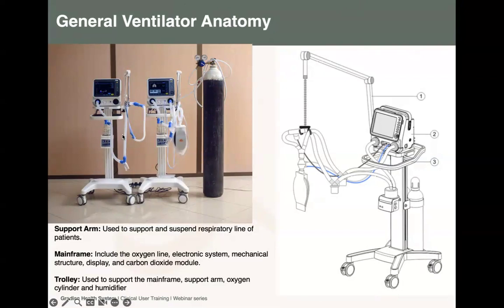Okay. So this below here, the left machine, this is an active humidifier in which the distilled water is filled here. And then this humidifier is connected to the inspiratory limb, and then it is going to the water trap, and then to the Y-piece, and then to the patient. This is active humidifier. And for HME, the HME is connected close to the end of the patient at the Y-piece. So this HME is not connected to the expiratory limb. So as you can see on the machine from my right side, the one which has been labeled with numbers, here close to the test lung, it's where the HME is connected. Okay. Next slide, please.